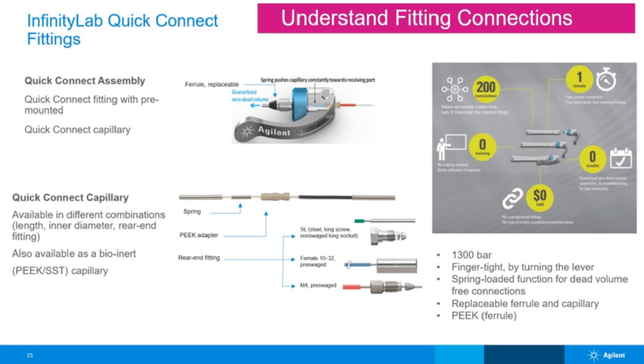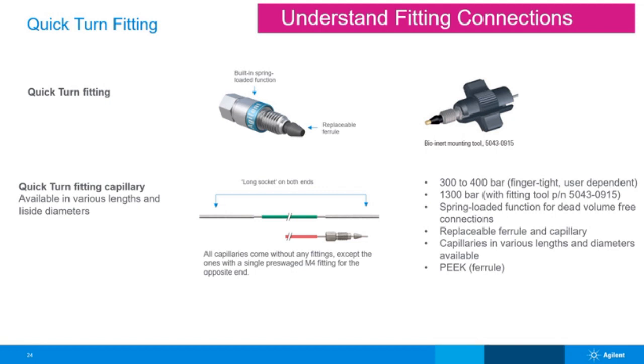The InfinityLab Quick Connect fitting is very well suited for low dispersion applications due to its guaranteed zero dead volume connection through the spring-loaded design. It's most beneficial for R&D, method development and contract labs, where users need to replace columns frequently, since it's much easier and faster to use than a standard fitting. The InfinityLab Quick Turn fitting has a similar design as the Quick Connect fitting, just without the lever. It is finger tight up to 400 bar, and with the use of the mounting tool, you can get up to 1300 bar.